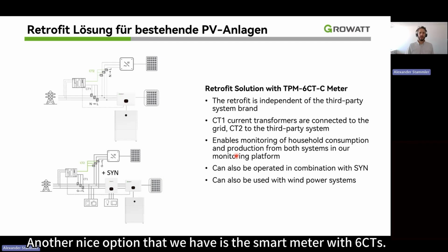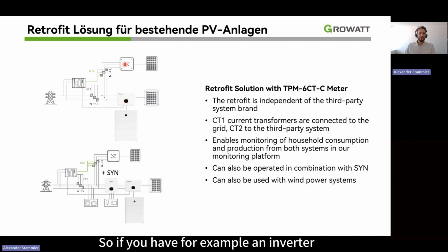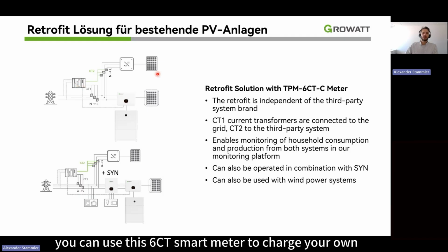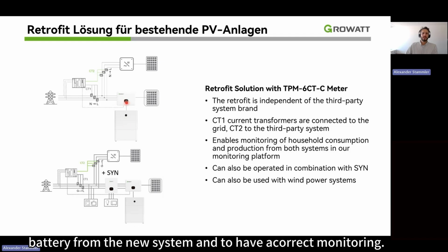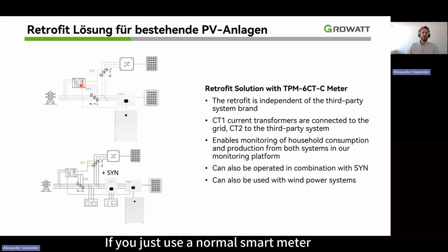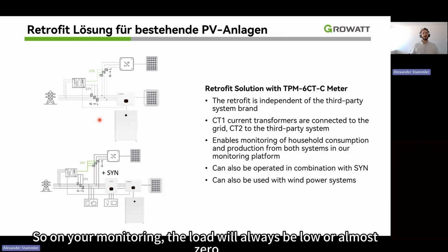Another nice option that we have is the smart meter with six CTs. So if you have, for example, an inverter from a different producer or from Growatt, which is an old system without battery storage, you can use this 6CT smart meter to charge your own battery from the new system, and to have correct monitoring. If you just use a normal smart meter, the monitoring will be totally wrong. Your household consumption will not be correct, because this inverter will produce energy which will flow into the household, and our system will not know this. So on your monitoring, the load will always be low or almost zero if this one is a big inverter.